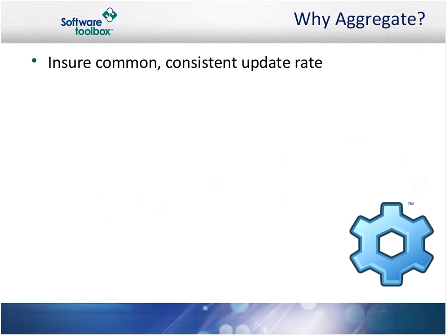If you have capacity limitations in your control network and want to ensure a random OPC client doesn't come in and overload it with an unreasonable update rate, then OPC aggregation is a way to accomplish some regulation of traffic on your control network. Aggregation also allows you to get OPC data to multiple OPC clients when the OPC server only allows a single OPC client connection for technical or commercial licensing reasons.